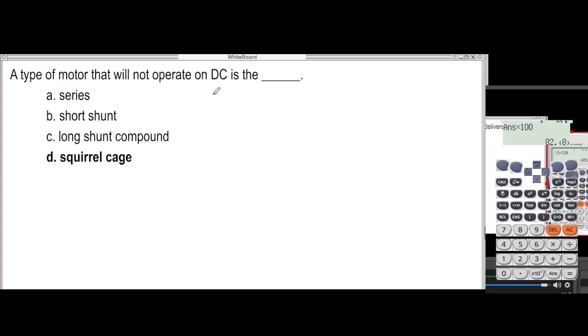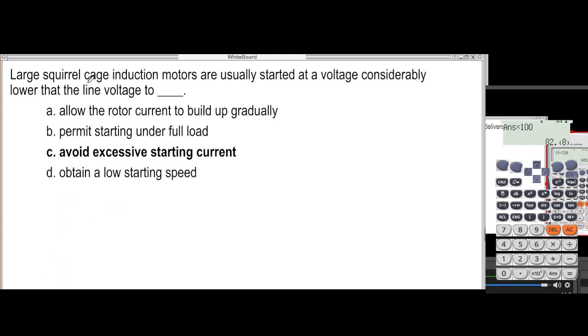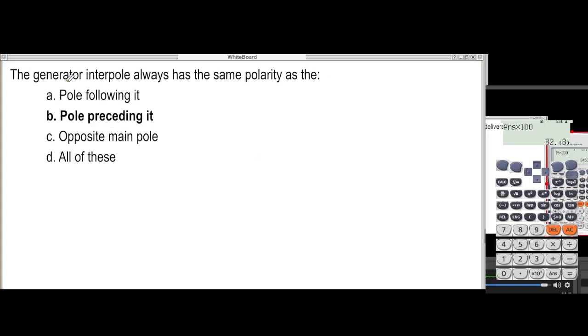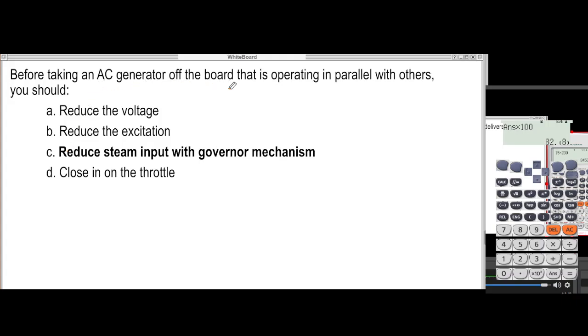The type of motor that will not operate on a DC, so ang tawag dyan is squirrel cage, because squirrel cage is only for AC motors. Large squirrel cage induction motors are usually started at a voltage considerably lower than the line voltage. Why? No, kasi at starting, medyo mataas din po ang kanilang starting current, which will damage its winding. Okay, the generator interpole always has the same polarity as the pole before it, so pole preceding it. Before taking an AC generator out of the board, no, kukunin natin yung ating nakaparallel. So, what is the proper thing we should do? So, kailangan nating pahinaan, no, yung ating governor o yung ating prime mover.